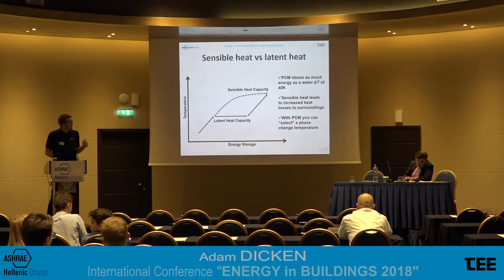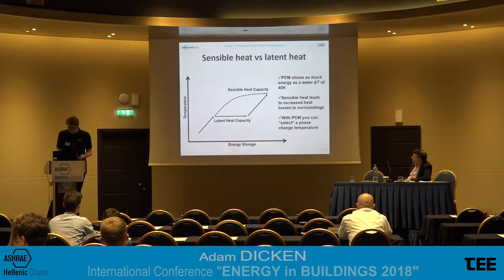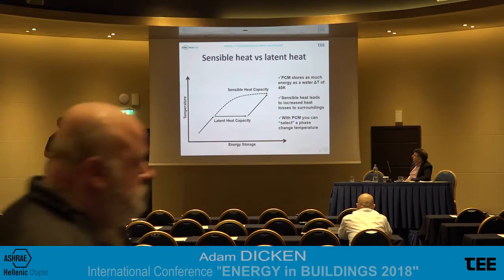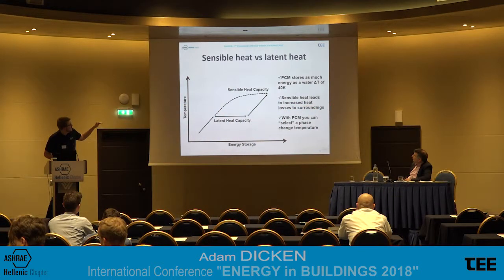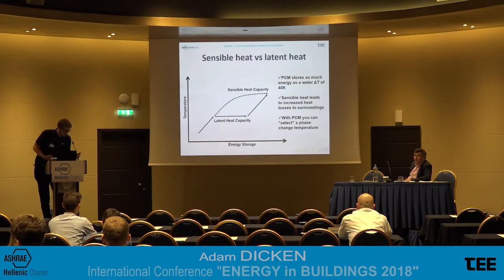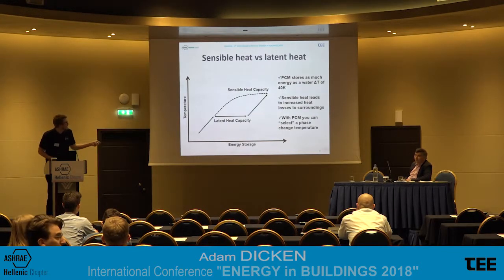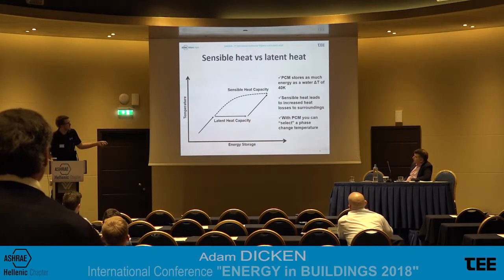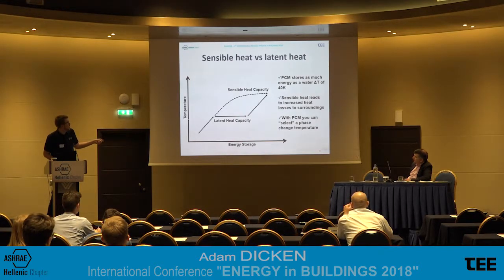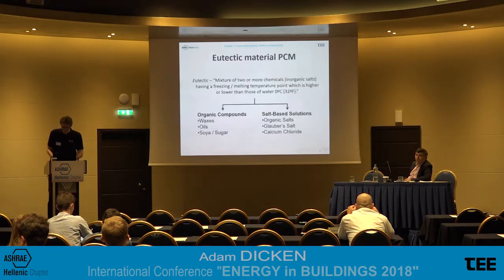With phase change material, we have quite a wide range, and you're able to almost select a temperature, which allows you to have a large amount of energy storage for a very low delta T. So were we to suppose this was, say, 40 degrees, then the temperature difference between 40 and 45, we'd have a much larger change in energy storage compared to sensible heat.